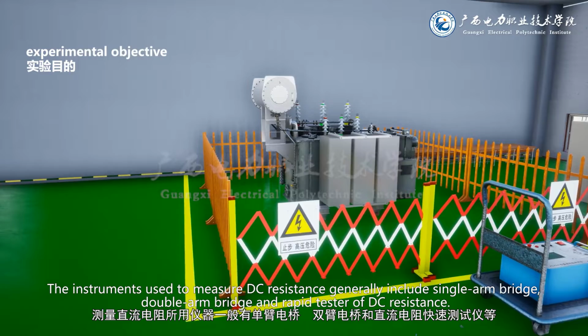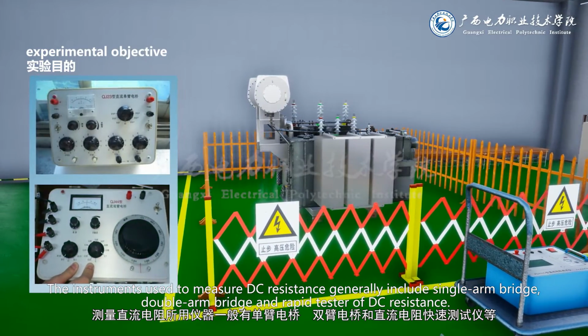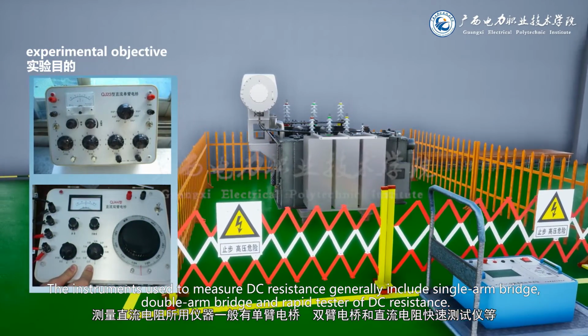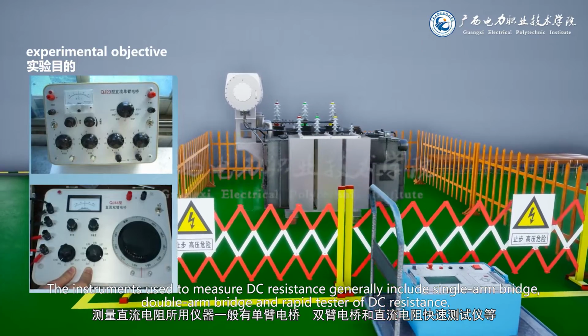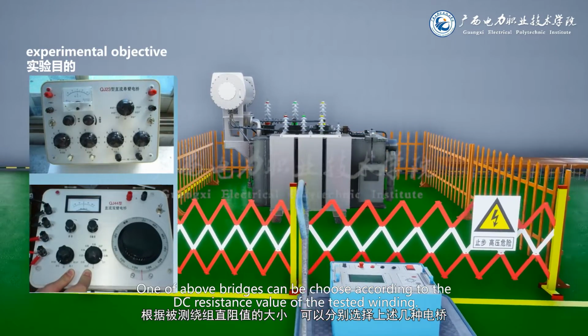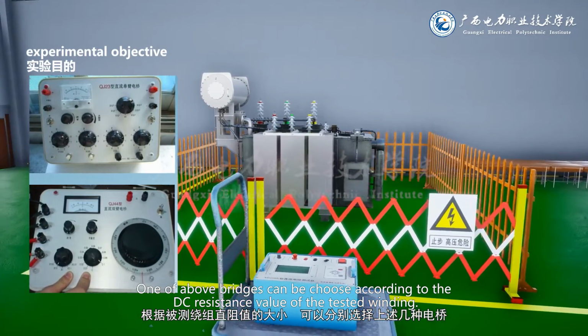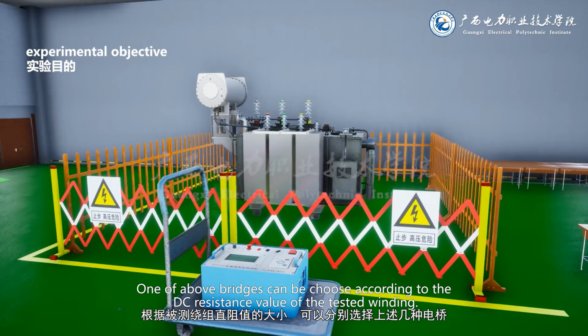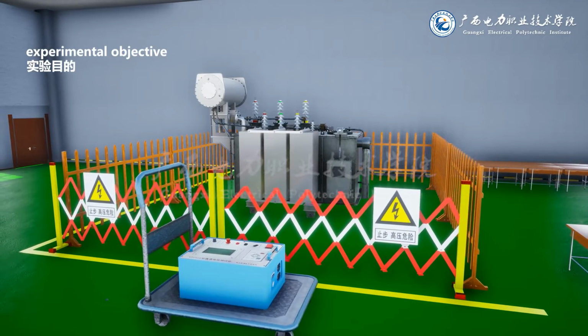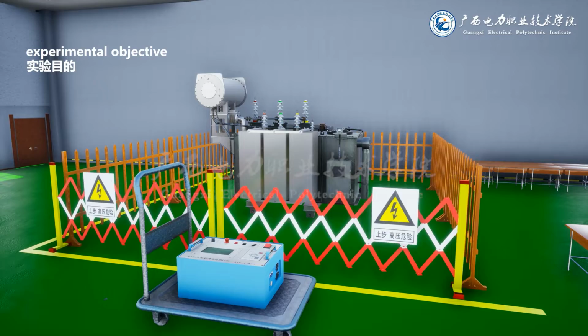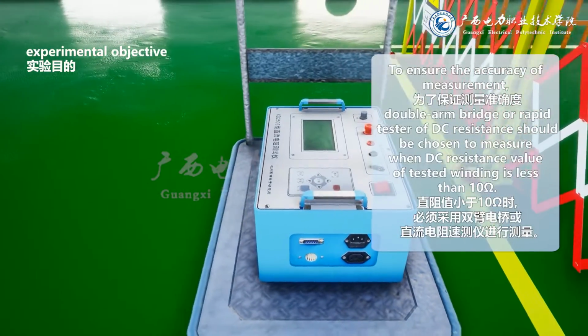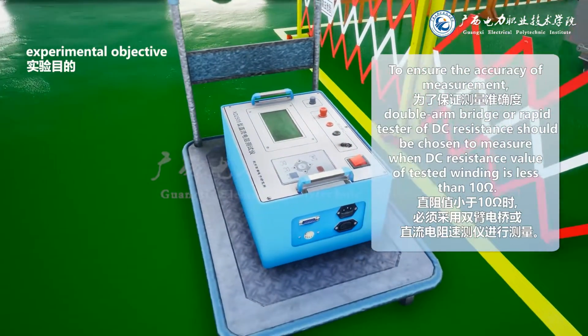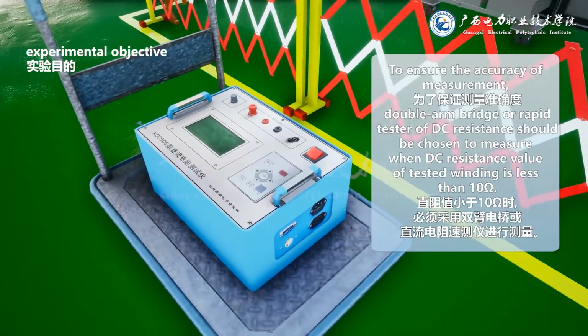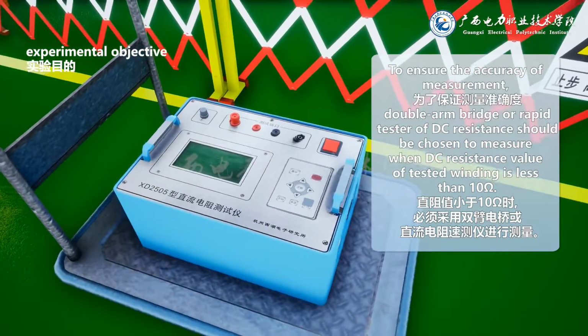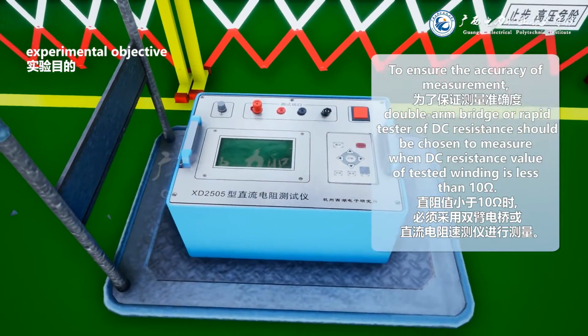The instruments used to measure DC resistance generally include single-arm bridge, double-arm bridge and rapid tester of DC resistance. One of the above bridges can be chosen according to the DC resistance value of a tested winding. To ensure the accuracy of measurement, double-arm bridge or rapid tester of DC resistance should be chosen to measure when DC resistance value of tested winding is less than 10 ohms.